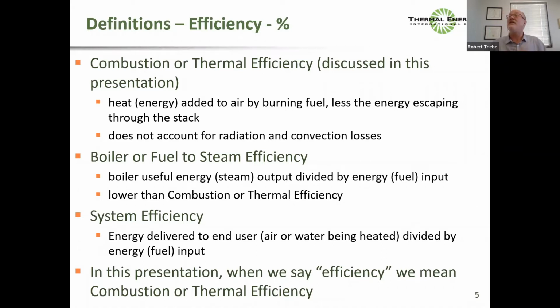Typically, when I'm talking about efficiency, I'm going to be talking about combustion or thermal efficiency, which is strictly the efficiency with regards to how much energy we're losing up the stack. It's the heat that the combustion produces and is delivered to the system minus the heat that goes up the stack. It doesn't account for radiation and convection losses. Different people use different names for these terms all over the industry, but I'm just defining how I'm using them.